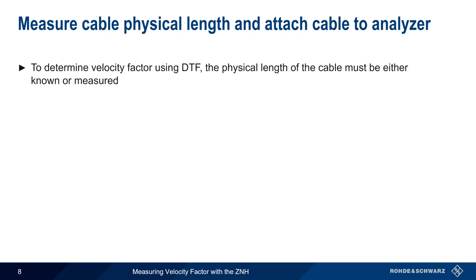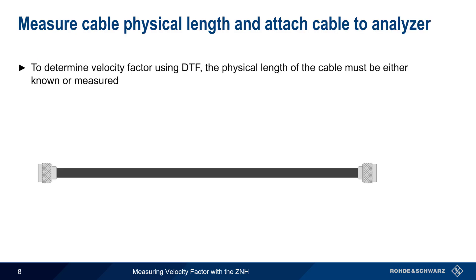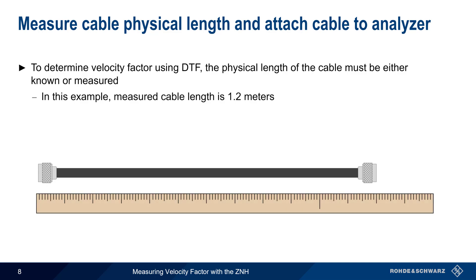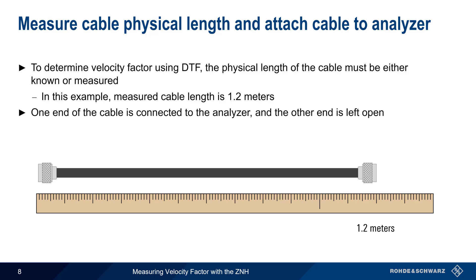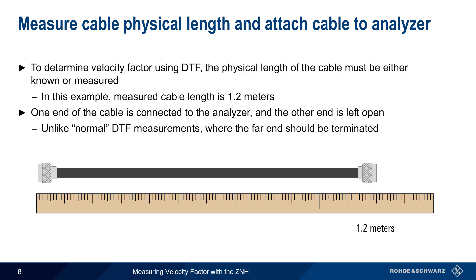In order to determine a cable's velocity factor with distance-to-fault, you must either know or measure the physical length of the cable. In this example, we'll be using a cable with a measured length of 1.2 meters. One end of this cable will be connected to the ZNH, and the other end will be left open or un-terminated. Note that this is unlike normal DTF measurements, in which we terminate the far end of the cable under test.